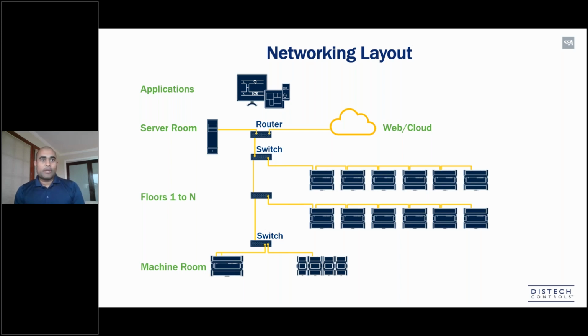Typically, what I recommend to people designing is, if your building is above 5 floors, I would recommend the riser to be fiber. It helps not just with speeds and performance, but also gets you future ready, because you don't know in 15 years what technology this building will have and how much data you'll need to transfer up and down. So I always recommend the vertical stack or riser to be fiber if you're going above 5 floors.